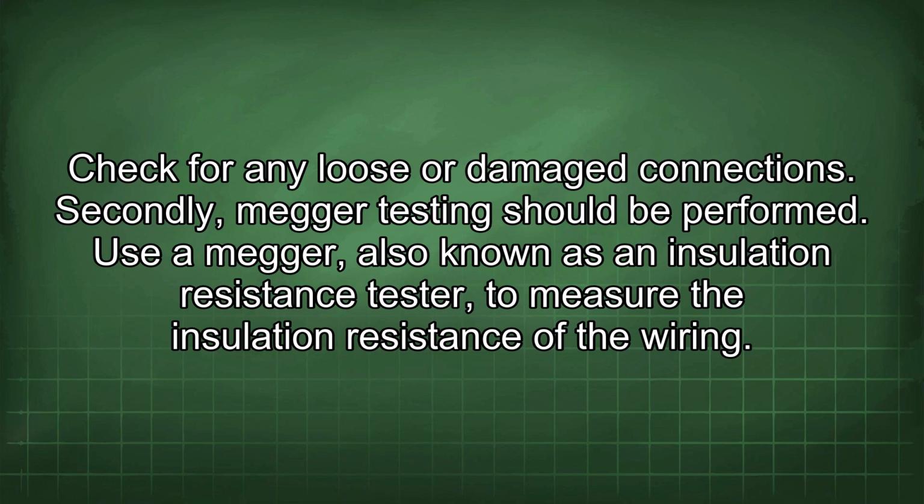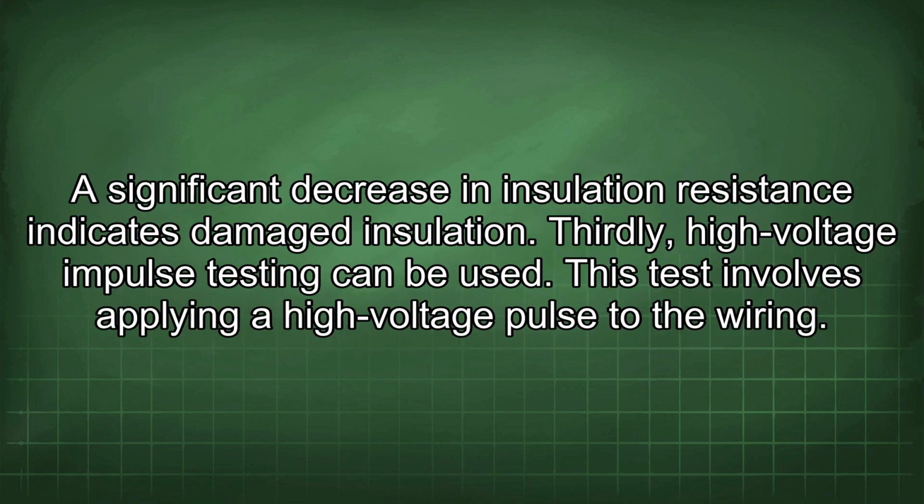Secondly, megger testing should be performed. Use a megger, also known as an insulation resistance tester, to measure the insulation resistance of the wiring. A significant decrease in insulation resistance indicates damaged insulation.